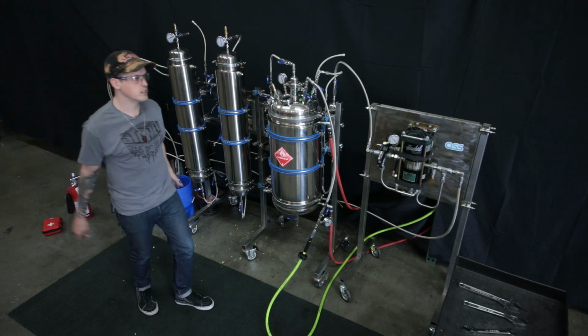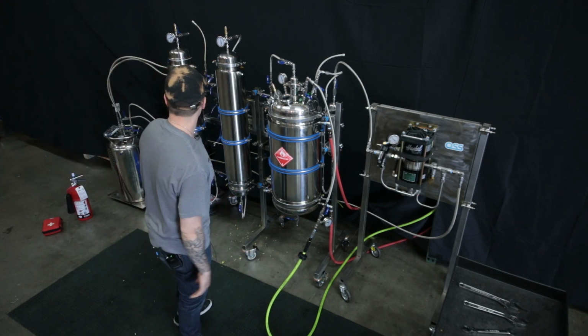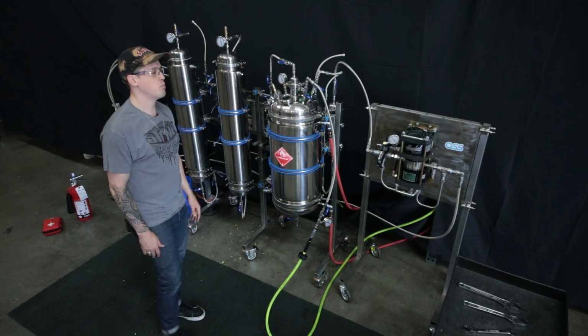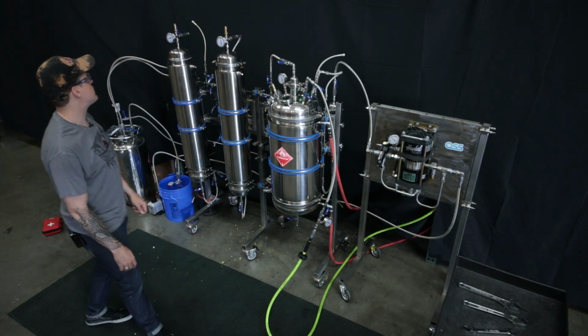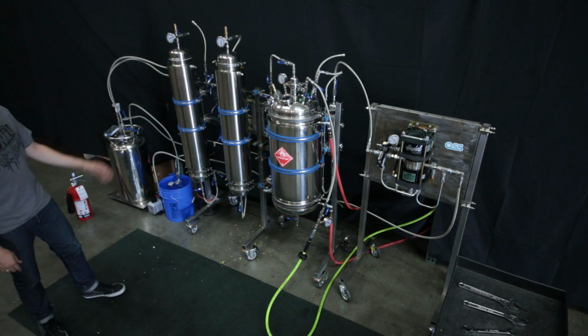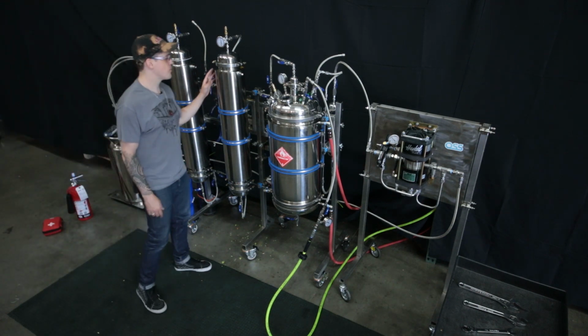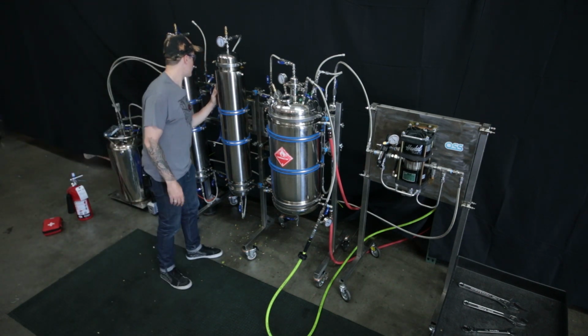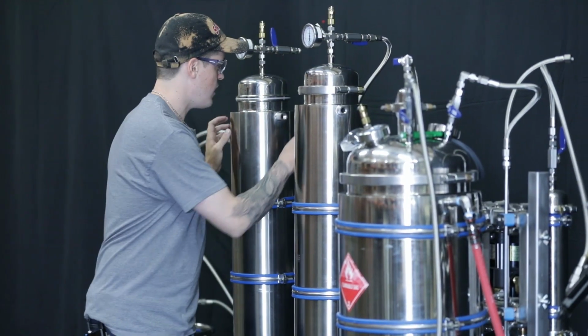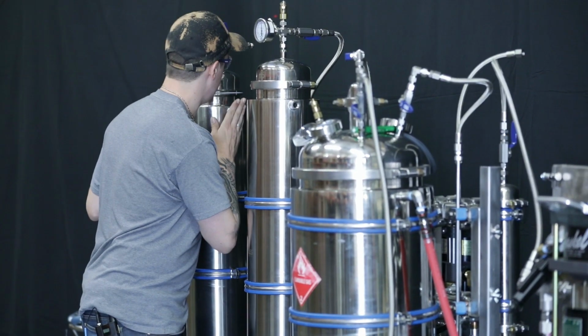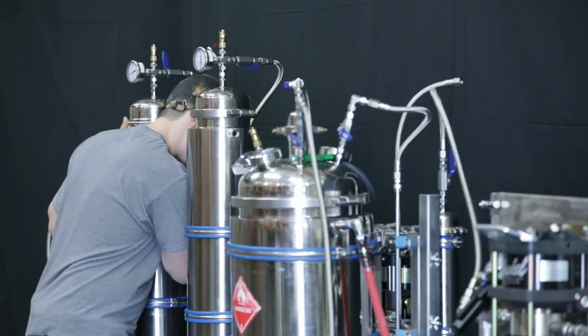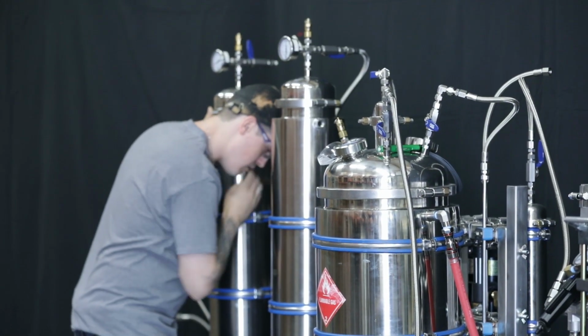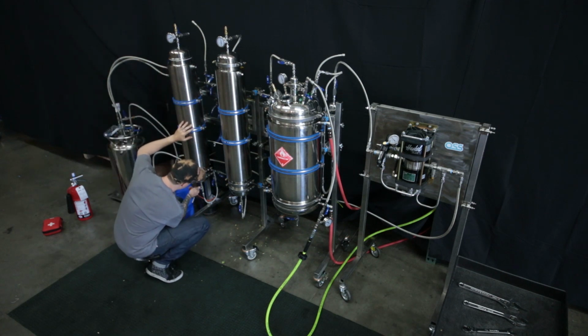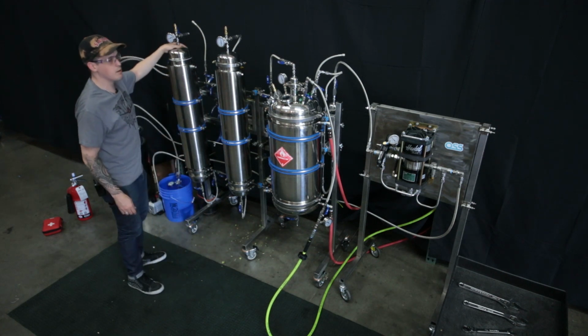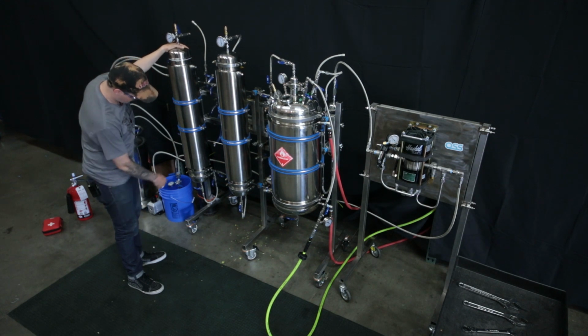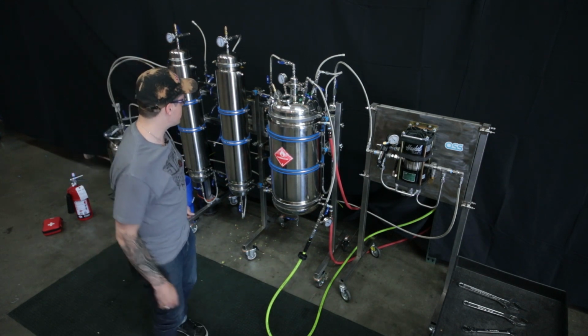In fact, I'll tell you we won't. Unless there's excess nitrogen in the system, we will likely see no pressure even near that. So as long as we're holding near 60, we should be solid for today. So again, I'm listening for any sort of loud hisses. I did hear a hiss coming out of this tube because that valve is just barely cracked down there, so I just closed that. We're good.